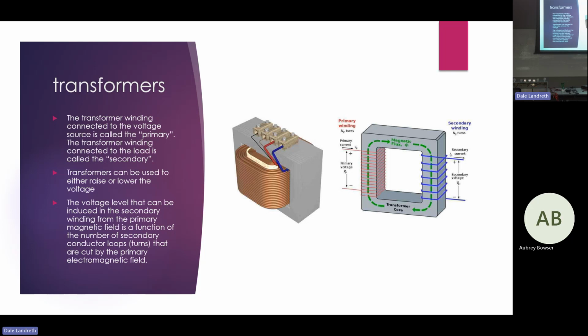I'll read this, I found it interesting—it kind of goes back to inductive reactance and stuff. The following steps explain the process of primary and secondary flow in a transformer. Step 1: when a load is connected to the secondary of a transformer, secondary voltage induced from the primary magnetic field causes current to flow through the secondary conductor winding. The secondary current flow in the secondary winding creates an electromagnetic field that opposes the primary electromagnetic field—so again, the secondary is opposing the primary, just like we talked about in the motor. So the flux lines—what are the flux lines?